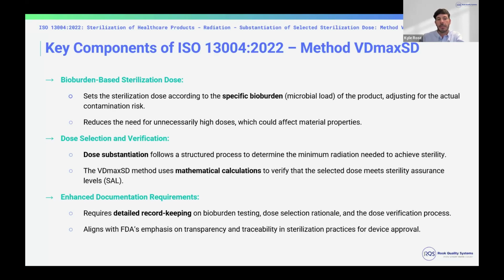So this happens a lot with companies that are outsourcing sterilization or using a contract manufacturer that's also doing sterilization. You still need to review the batch records of sterilization and have those in your quality system. So for the actual ongoing compliance within the quality system, you need to make sure you have these records and you're verifying that each dose met your SAL and your VD max calculations that you set up with the sterilization validation.